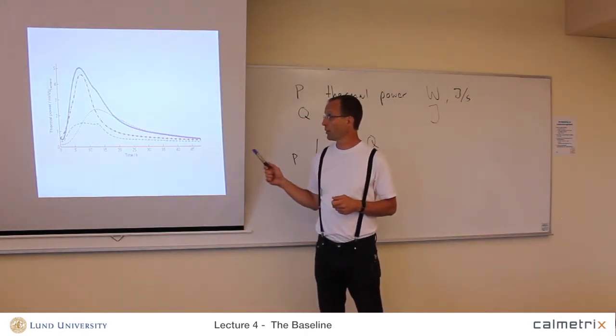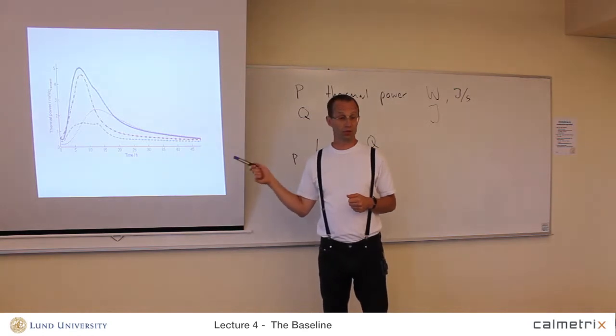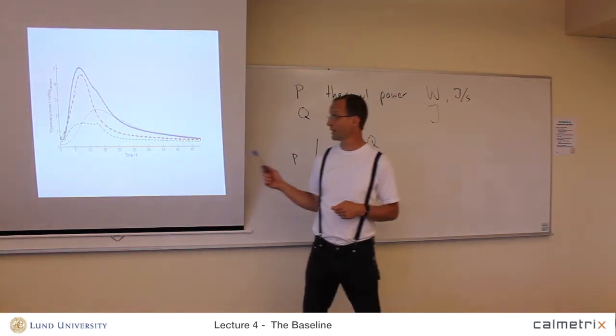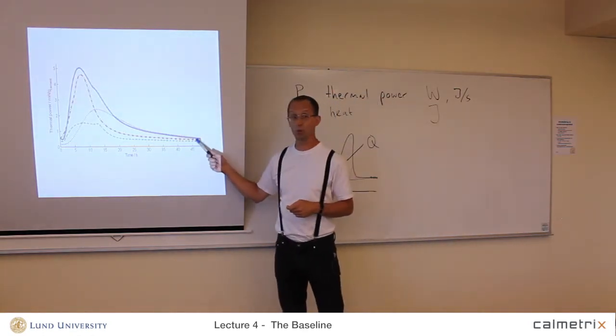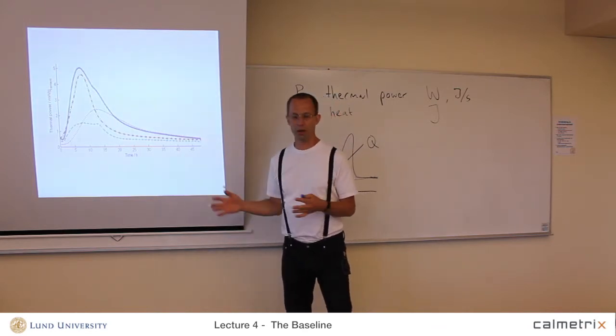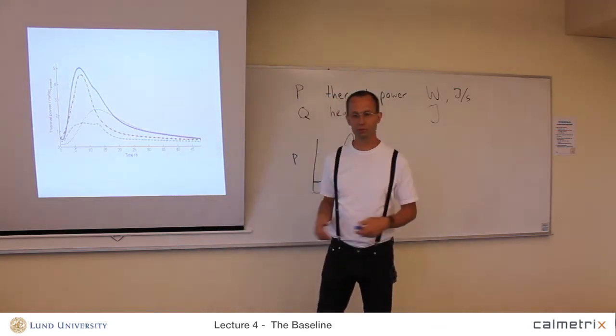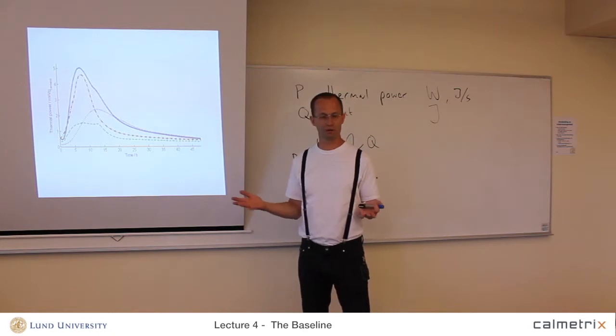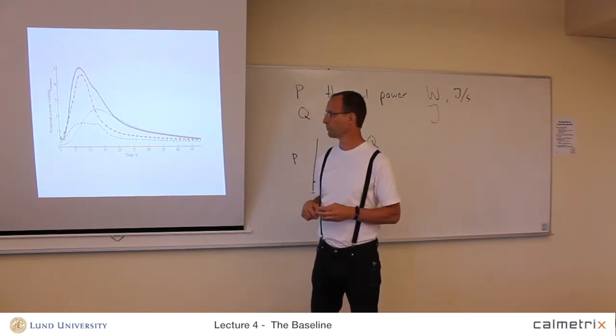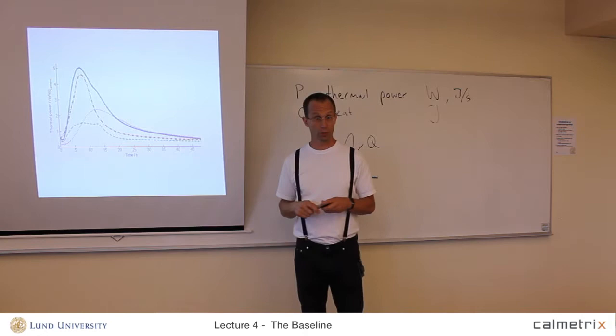The cases where you do need to re-measure the baseline are: if you change temperature, because baselines usually change quite a lot with temperature; and also if you move the calorimeter from one room to another, or if there's a power failure or similar disturbance — then it can be good to re-measure the baselines.